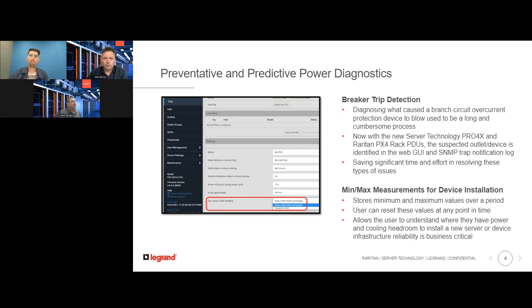Also, though we can tell you the power consumption at a particular point in time, what's really important is looking, let's say, over the last year and understanding your absolute worst case of both temperature and power consumption. With our new min-max feature, we can let users know what the greatest power draw was in that cabinet over, let's say, a year's period of time, and what the worst temperature is. So if my max consumption or worst case is Black Friday or whatever happens to be, we can go back and look at that.